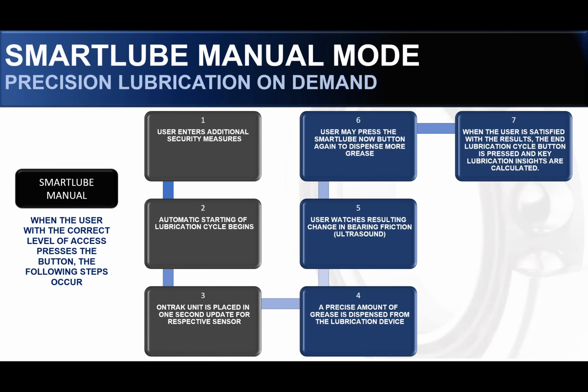What we can do is put that specific sensor into 1 second update. So no matter where you are in the world, it is like you're standing next to that bearing, capturing real-time friction. Lubrication gets dispensed. That precise amount of lubricant gets dispensed, and you watch the resulting change in friction to ultimately decide if you want to put more lubrication into it. When you're satisfied with the results, you end lubrication, and it's going to calculate all the grease that was used and all that information I've been talking about.